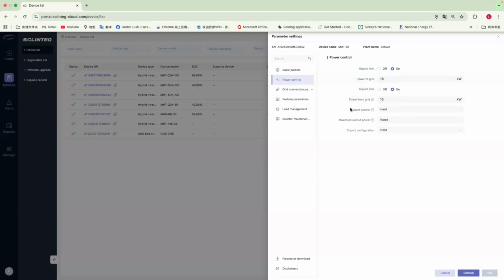This parameter over here, the export control, is for situations where the inverter has lost communication with the smart meter or the data logger. In this case, the inverter cannot receive the real-time requirement from the grid side. There are two options to set. First is the hard mode. If we choose the hard mode and the inverter loses communication, for example with a smart meter, the inverter will stop generation directly and immediately. If we choose the softer option, once the inverter has lost communication with the smart meter, it will run at the value we have set here.